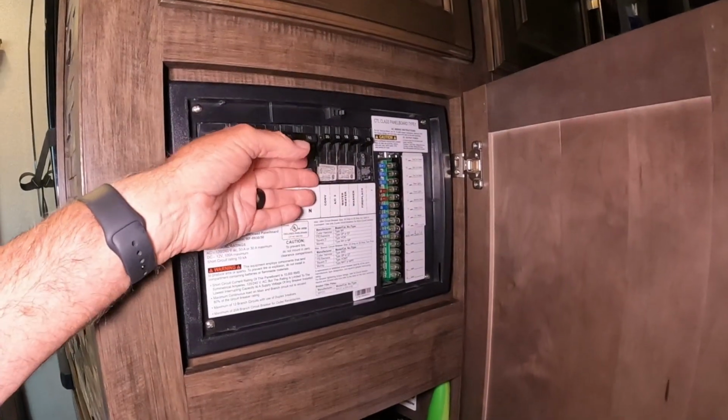So over the last few months, we've noticed a buzzing coming from our breaker panel, and Shelly occasionally saw the bathroom lights flicker and an occasional, for lack of a better word, ozone smell. This led me to open the panel, our breaker panel. Other than occasionally having to reset the main double pole 50 amp breaker when the pedestal was turned on, they all seemed fine. Then I touched them. Oh my gosh, hot. No, really hot.